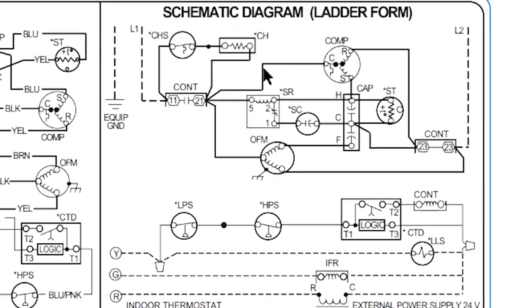Going through the compressor: common is connected to L1 through the compressor contactor. The only way the compressor can come on is if the normally open contactor switch closes — the path across the switch must be made for current to travel through and power the compressor. Inside the compressor there's a normally closed, open-on-rise thermal switch. If the temperature rises, this switch opens — that's the thermal overload. Common is not a winding; it's just a point between the run and start windings.